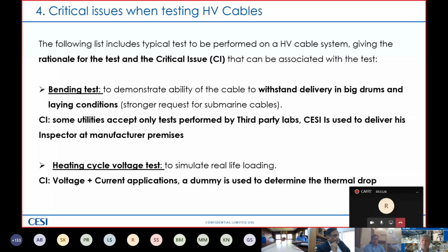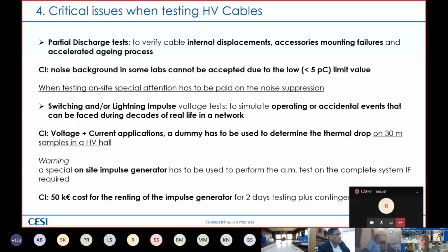Heating cycle voltage test. These are performed to simulate a real-life loading. So we have a voltage plus current application, and as I said, a dummy is used to determine the thermal drop. As I already said a couple of times, partial discharge tests are suggested to verify cable internal displacement.